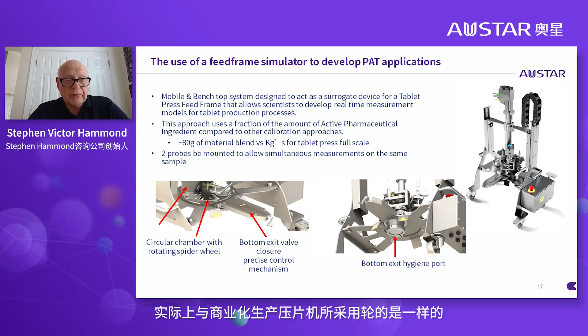So inside that feed frame there is a rotating paddle wheel, which is identical to those actually in the commercial manufacturing tablet press. Work has been published by Pfizer on the use of the simulator to develop calibrations remotely from the tablet press that can actually run in commercial manufacturing. In fact, in this case, what was desired was to develop one calibration in the simulator that would work on two identical tablet presses, in one location in the USA and another location in Germany.